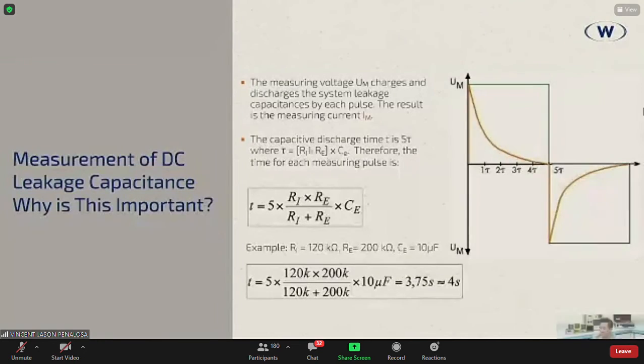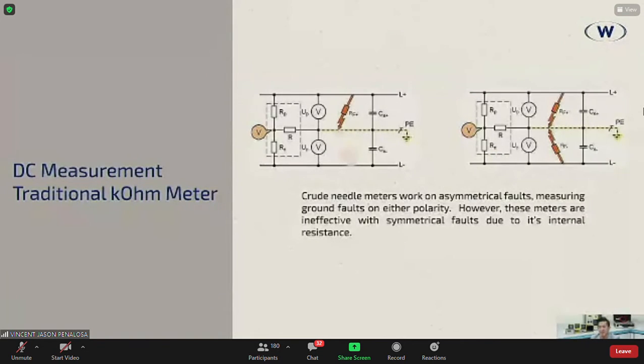Okay? So, we have here what we call a traditional kOhm meter for DC measurement. They're basically crude needle meters. They work perfectly on asymmetrical faults. When we talk about asymmetrical faults, it's just one fault to ground. It's either on the positive side or on the negative side. However, when the faults become symmetrical, more often than not, they fail to work.